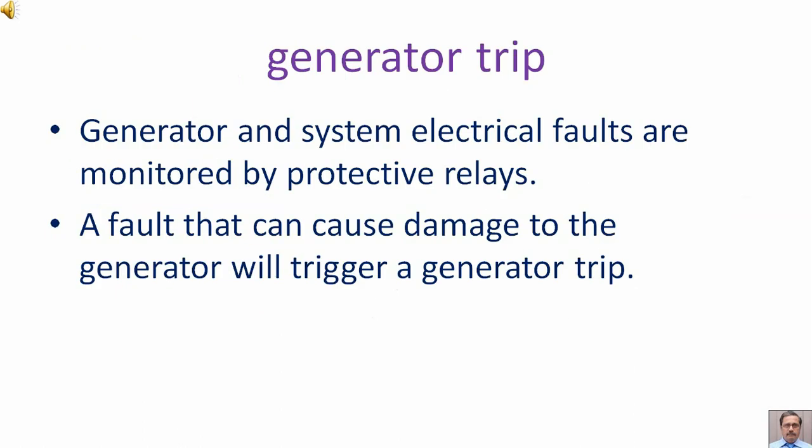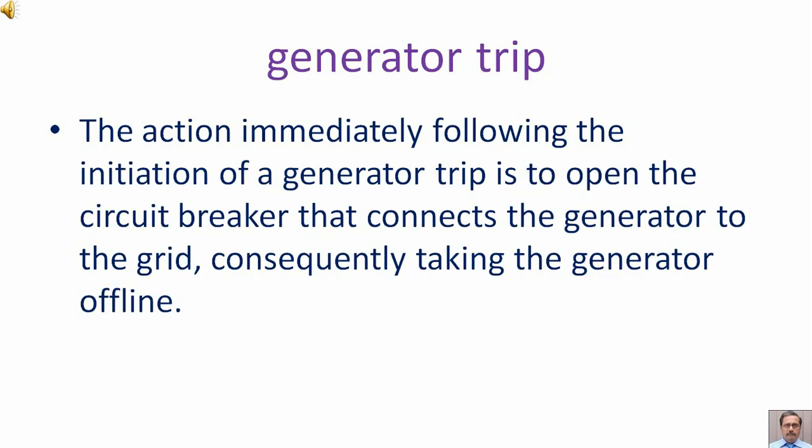Generator trip. Generator and system electrical faults are monitored by protective relays. A fault that can cause damage to the generator will trigger a generator trip. The action immediately following the initiation of a generator trip is to open the circuit breaker that connects the generator to the grid, consequently taking the generator offline.